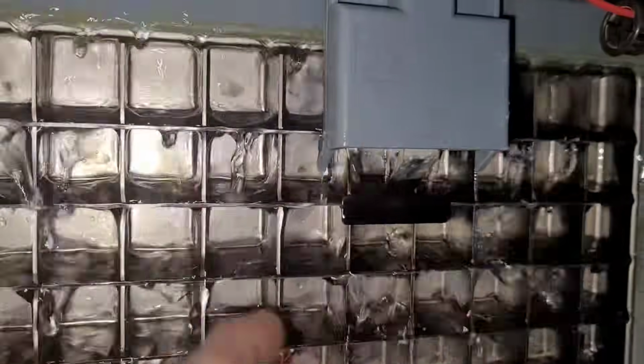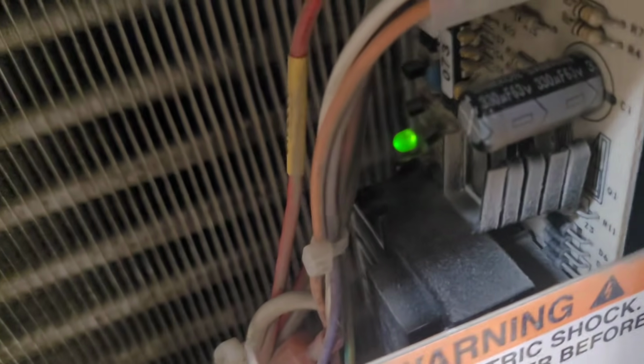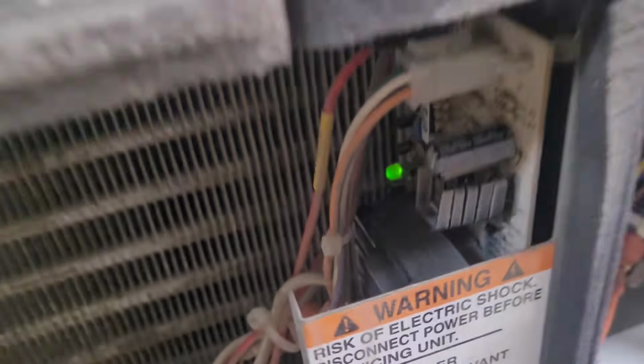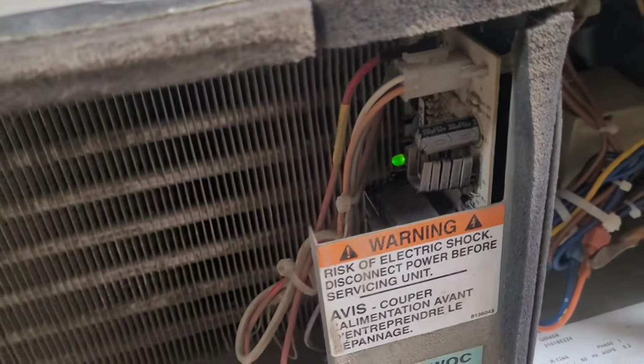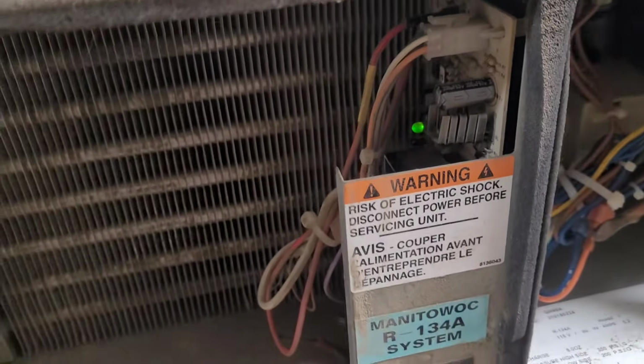You can see we kind of have some water movement across here. If you look at the board, there's a green LED and a red LED. The red LED should only light up once there's enough water contacting the probe to cycle a harvest cycle. So if I touch from the probe to the thing there, you can see that LED comes on. When I remove my finger, it shuts off. On, off.